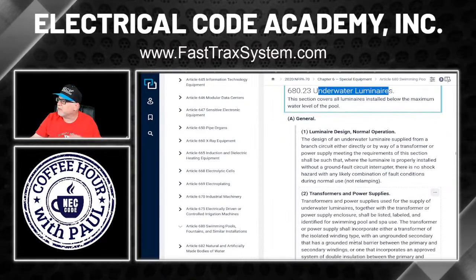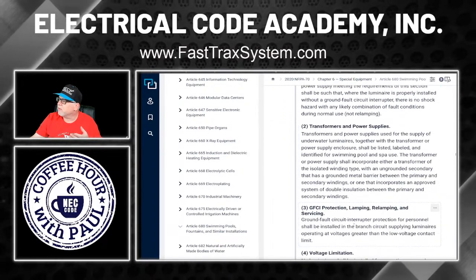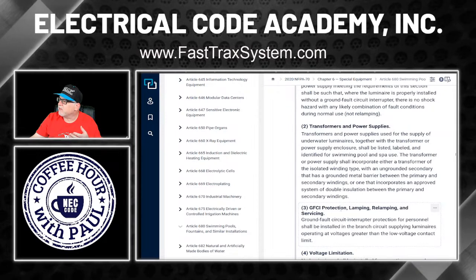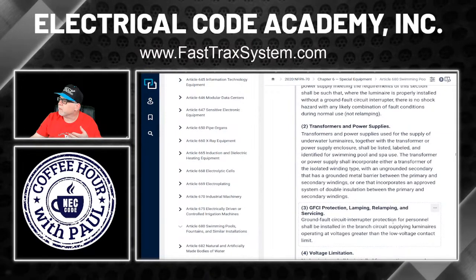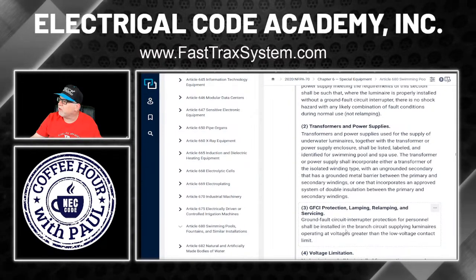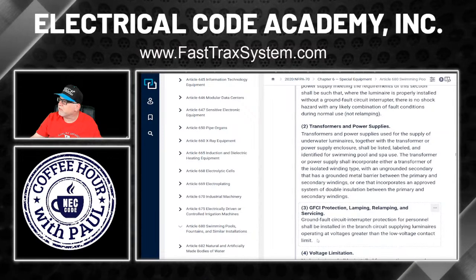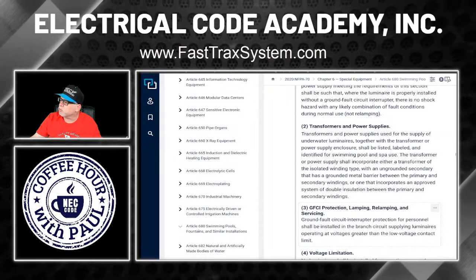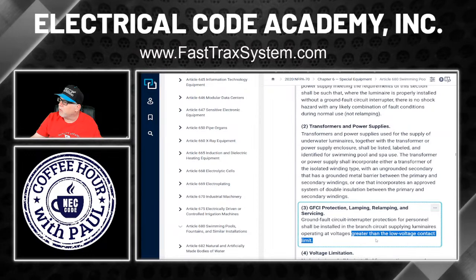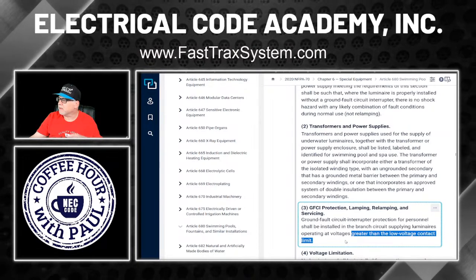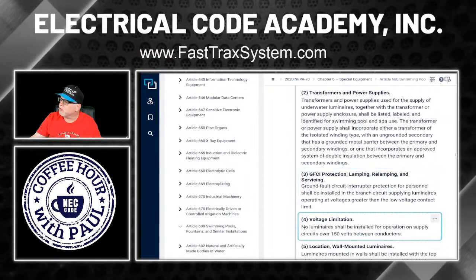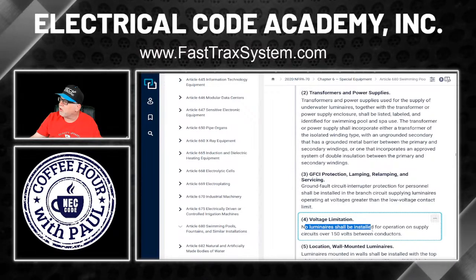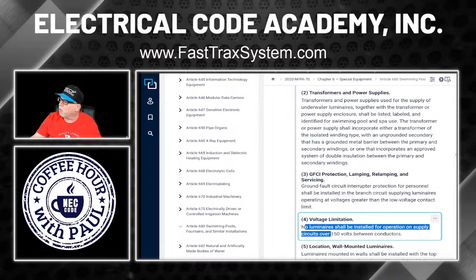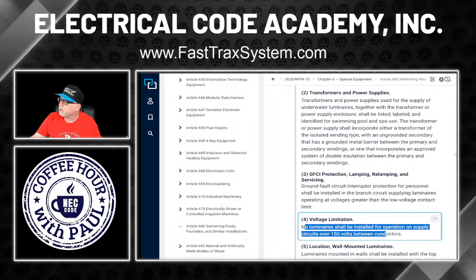All right, so now my trigger is the voltage. GFCI protection. Ground fault interrupter protection for personnel shall be installed in the branch circuits supplying luminaires operating at voltages greater than the low voltage contact limit. Okay, now, it also says no luminaires shall be installed for operating on supply circuits over 150 volts between conductors.